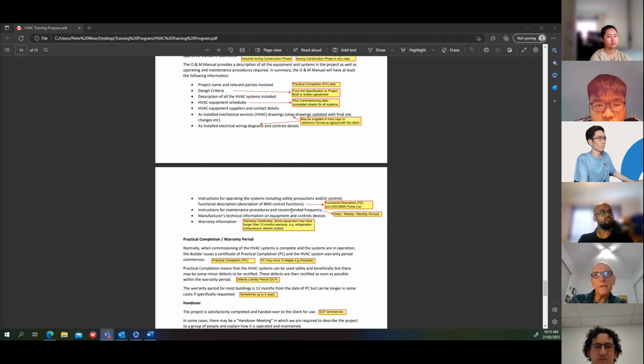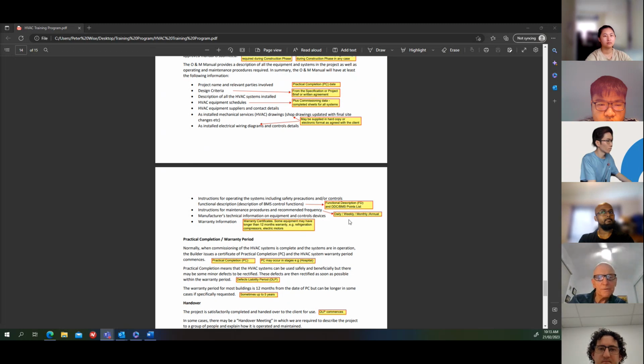Instructions for maintenance procedures and recommended frequencies: there might be things required daily, weekly, monthly, or annually. Daily, probably not that many things, but weekly you might just check that everything's running correctly, with no funny noises. Monthly, you might look at the filters. Annually, it's really repeating all the monthly procedures, but also if you've got, say, chillers in the project, there might be annual procedures you need to follow, like cleaning out the tubes of the chiller or things like that.